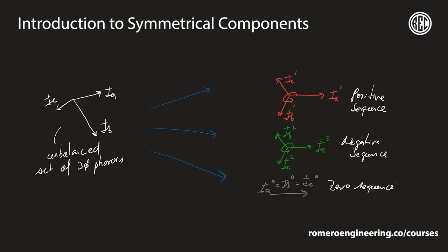This decomposition applies to both currents and voltages — for example, VA1, VB1, and VC1 for the positive sequence voltages. One important point: when dealing with symmetrical components, the voltages are always phase-to-neutral, not phase-to-phase. In power systems we're typically given phase-to-phase voltages, but symmetrical components always uses phase-to-neutral voltages.